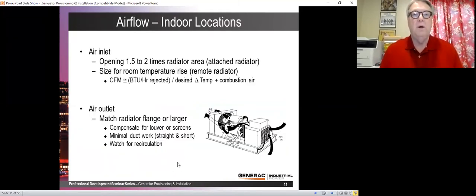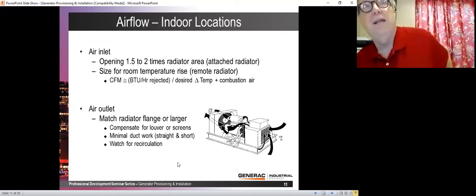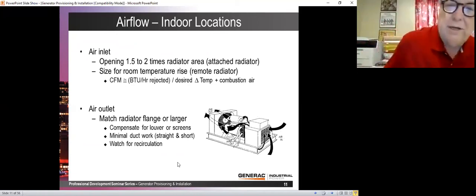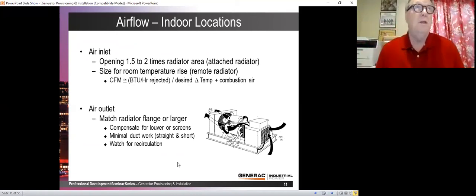Here's the air inlet. We already talked about this, the opening into the room. This would be for an indoor generator, 1.5 to 2 times the radiator area. And there is a formula so that you can calculate this. And then the air outlet, we should match the radiator size and then flare out to the louvers on the outside of the building. Make sure, of course, that your air inlet and your air outlet are on 2 different sides of the building. I've actually seen some locations where they had the air inlet and the air outlet right next to each other, and it's worked okay. I haven't seen a real problem, but clearly that means that hot air going out can turn right around and come back in the air inlet, and that's not really what you want.